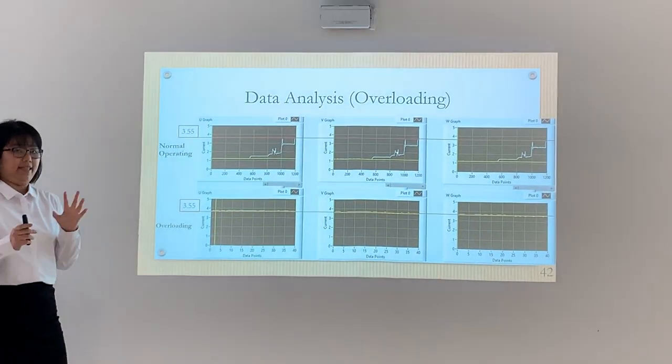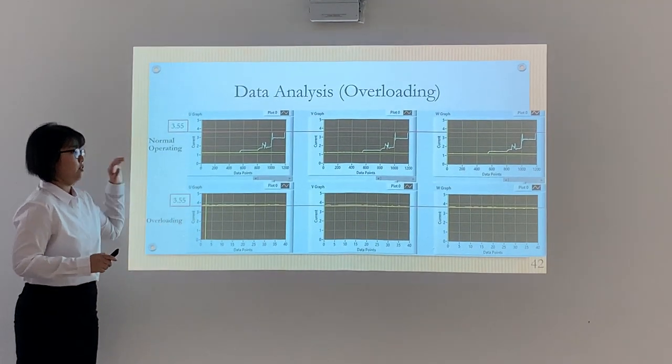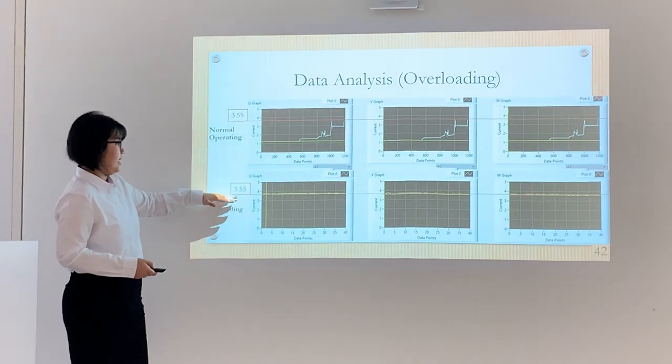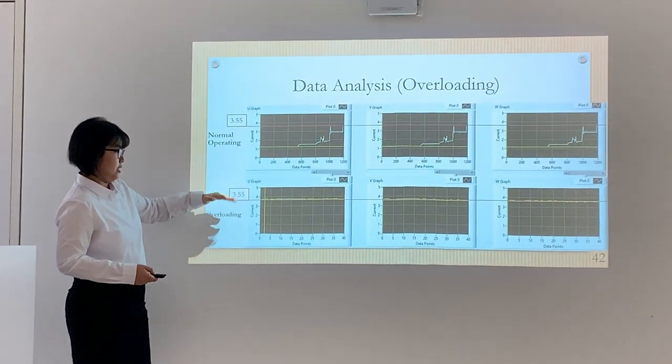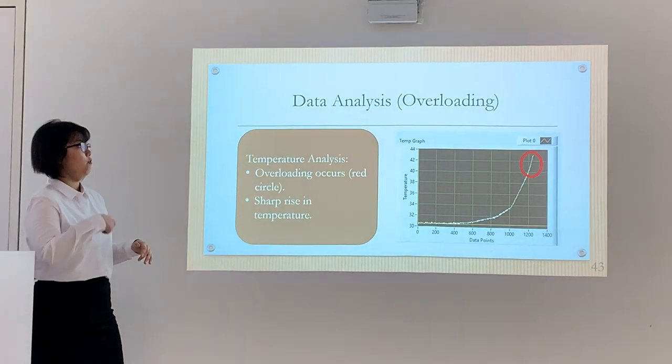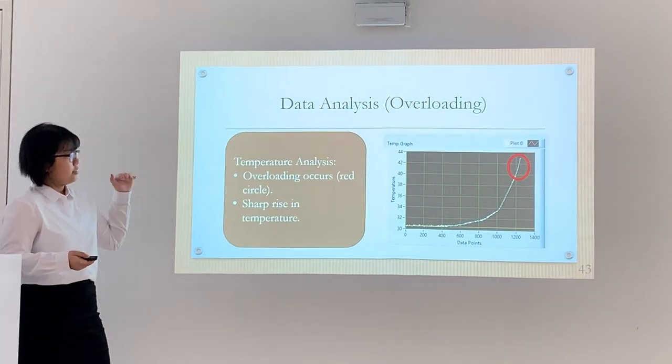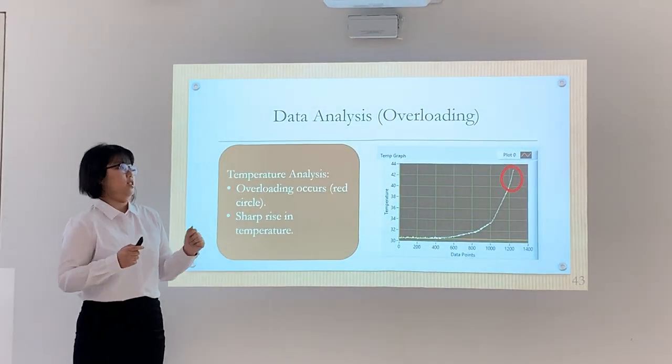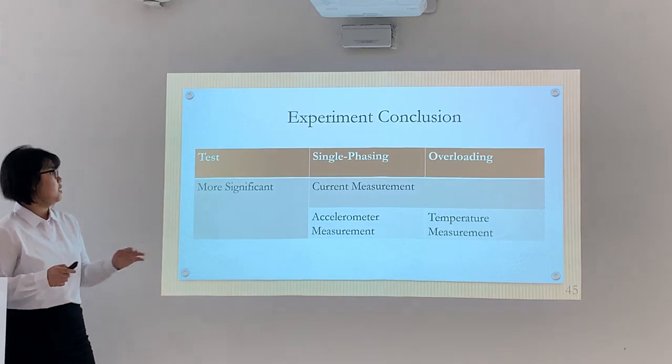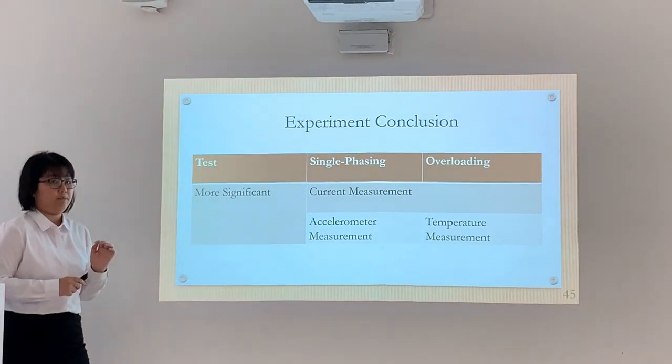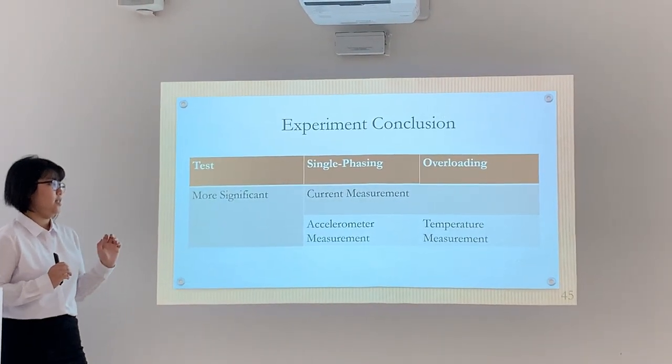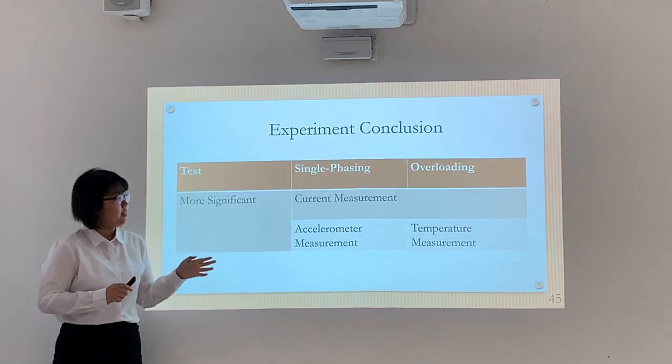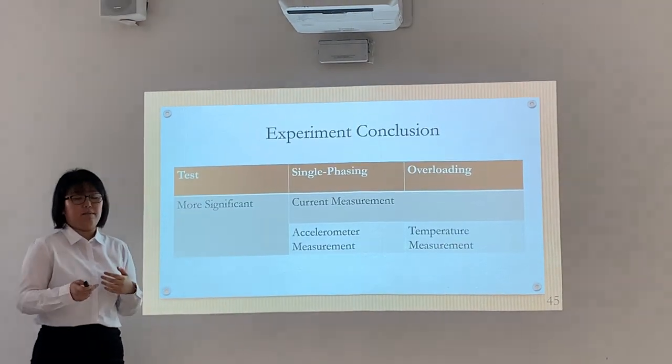Next is the overloading analysis. The red line means the current is above the rated current for the motor which is at 3.5 amperes. In this case the current is above the red line. For overloading, the temperature shows a spike with red circle, and this is where the fault occurs. In conclusion, current measurement is significant in both tests. But individually, single phasing is significant with vibration measurement, and overloading is more significant with temperature measurement.